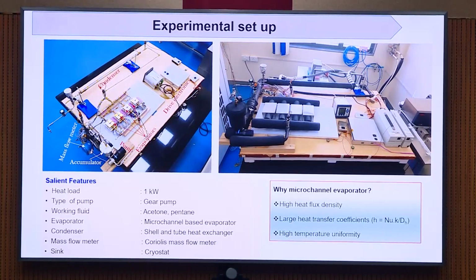This is the device which we have fabricated, tested and realized. We have done testing up to 1 kilowatt, and the pump we have used is a gear pump, and the working fluids we have used are acetone and pentane, because our operating temperature is between -22 and plus 80. The evaporator is a microchannel based evaporator. Why? Because a microchannel evaporator will have high heat flux density, high heat transfer coefficient, and high temperature uniformity compared to normal tubing. For the mass flow meter we have used a Coriolis mass flow meter, and the sink is the cryostat.